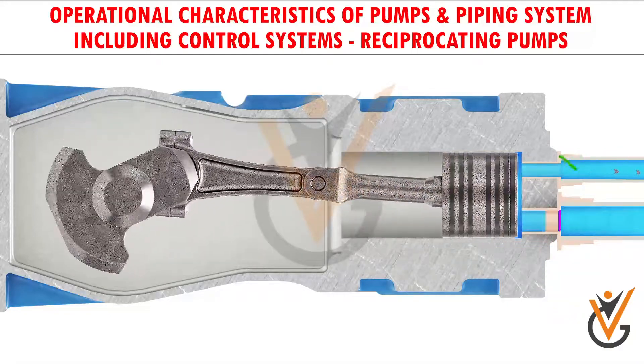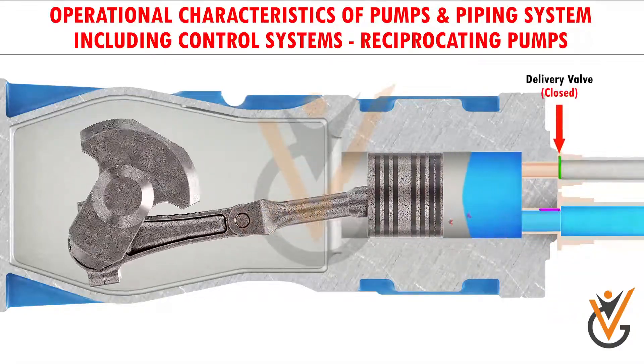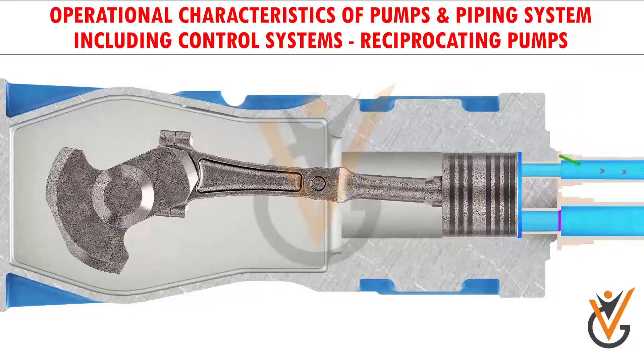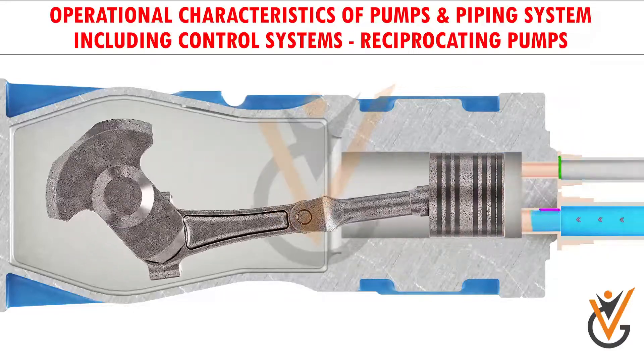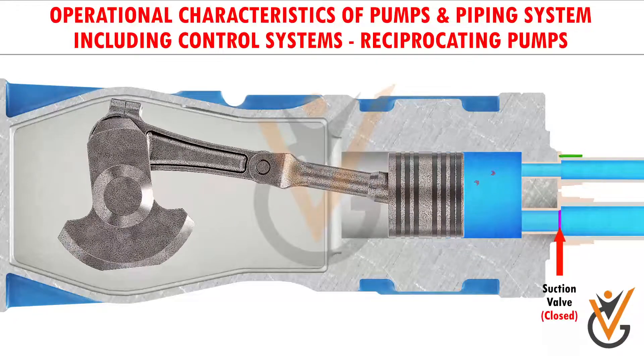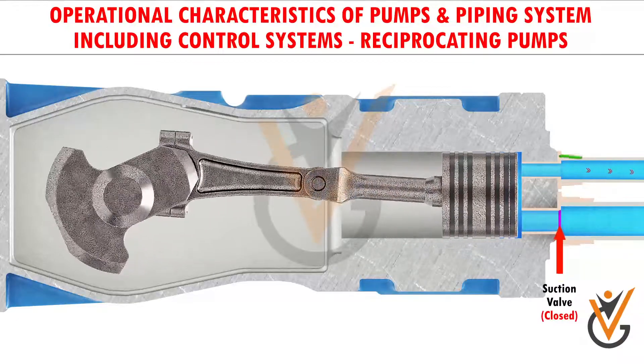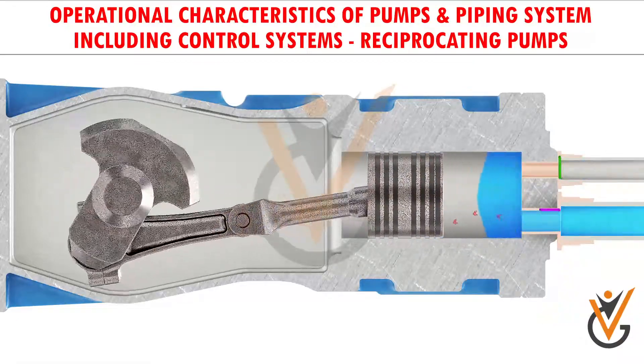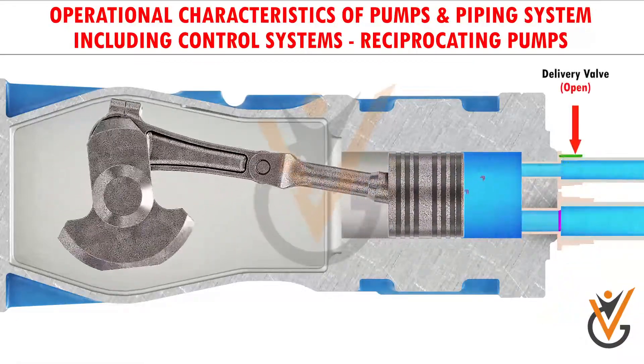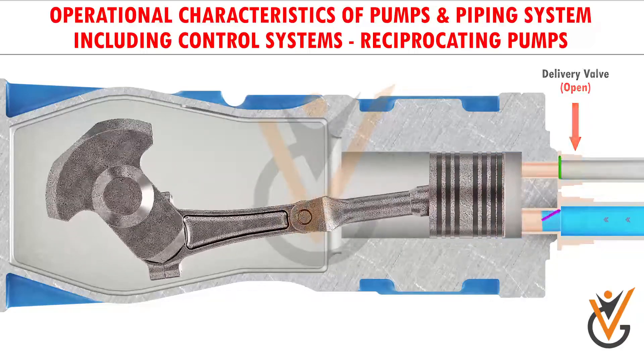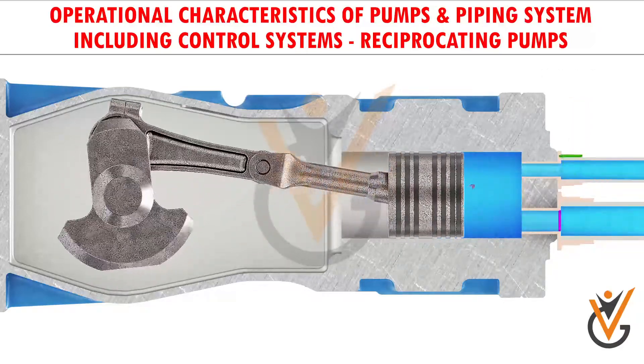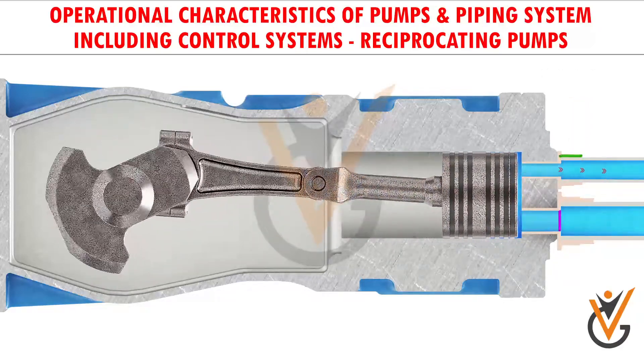During this time, the delivery valve remains closed. As the piston starts moving towards the left, the suction valve closes and the delivery valve opens. Due to the pushing action of the piston, the water goes out from the discharge valve to the delivery side. This is how the single acting reciprocating pump works.